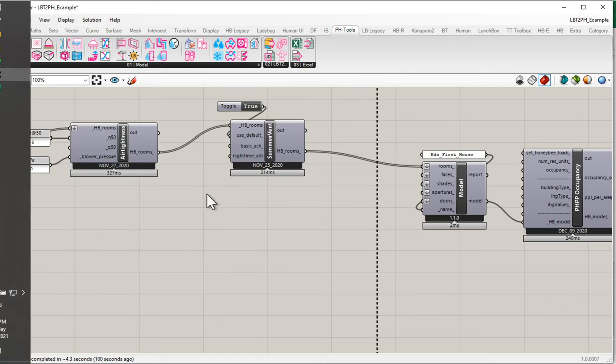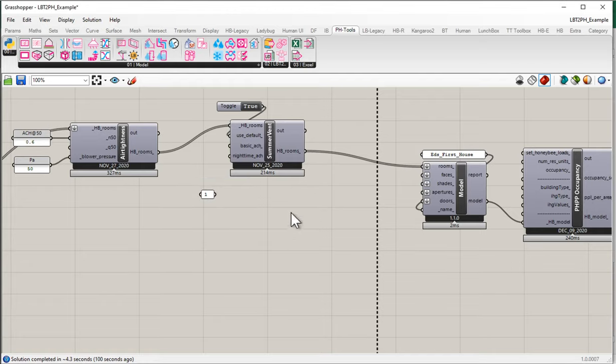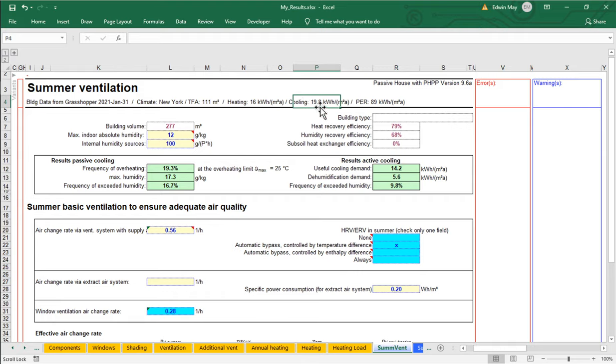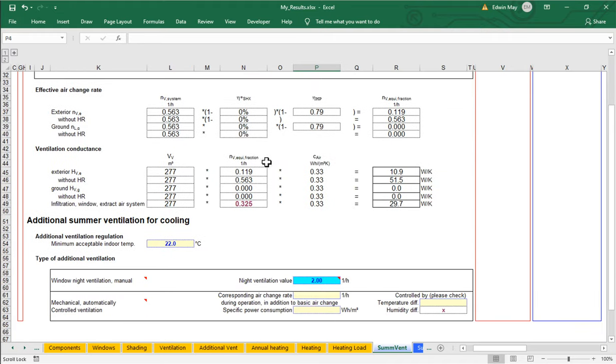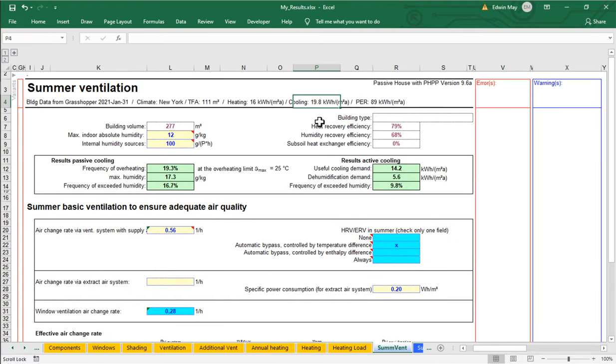For instance, if we come in here and let's say that we go up to 1 ACH at night because we leave all of our windows wide open, how is that going to affect our project? So once that flows through, we'll take a look at our PHPP. Notice here, our cooling is now down to 19.8. So bumping up that nighttime ventilation to a much higher ventilation rate. Notice it's at two. Remember that one ACH, it's applied to both honeybee rooms. So we have two ACH at night, which is pretty high, but that helps us cool the building significantly. If we really were able to get that much airflow at night, if that was realistic based on our site and security and the way the users use the building and the amount of operable windows that we've built into the building, then that can hugely help our cooling energy demand and overheating risk issues for the building. That can be really impactful.